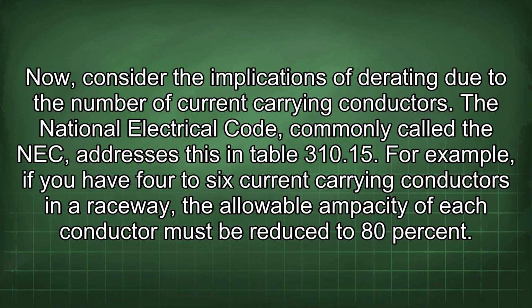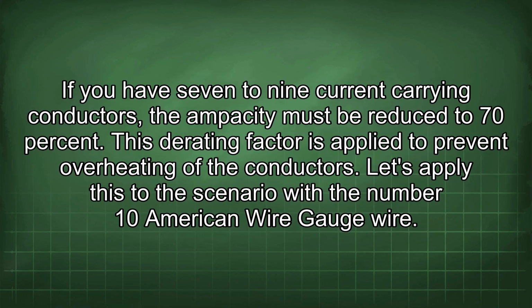Now, consider the implications of derating due to the number of current-carrying conductors. The National Electrical Code, commonly called the NEC, addresses this in Table 310.15. For example, if you have 4 to 6 current-carrying conductors in a raceway, the allowable ampacity of each conductor must be reduced to 80%. If you have 7 to 9 current-carrying conductors, the ampacity must be reduced to 70%. This derating factor is applied to prevent overheating of the conductors.